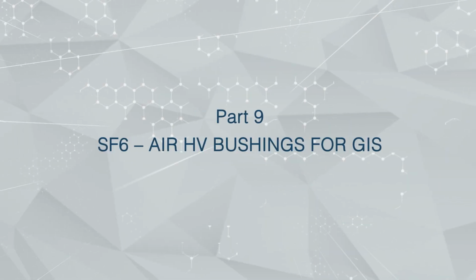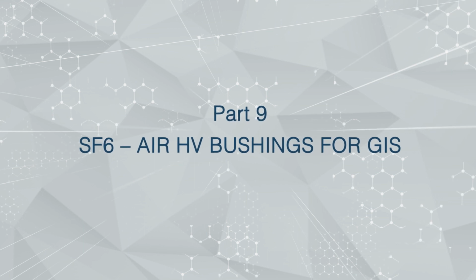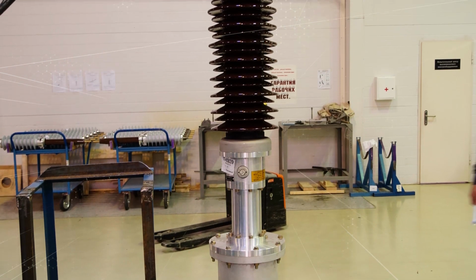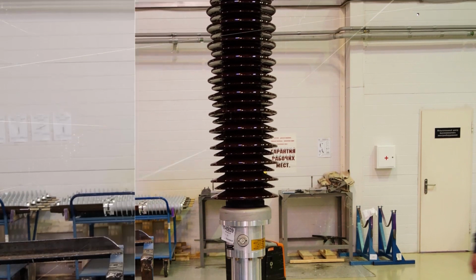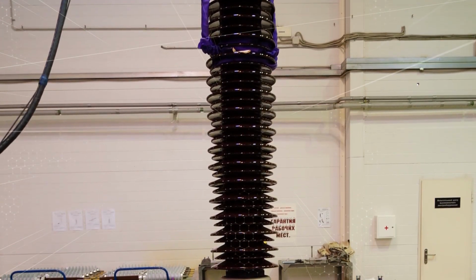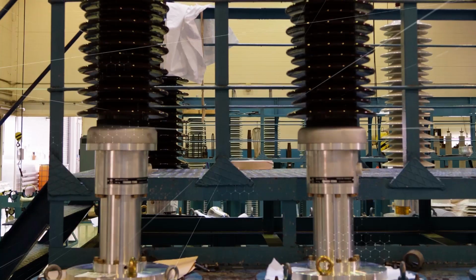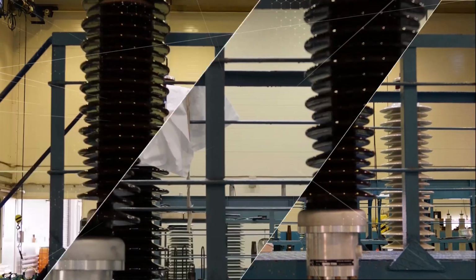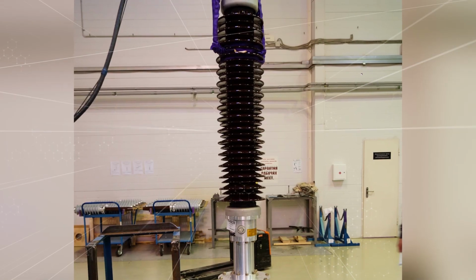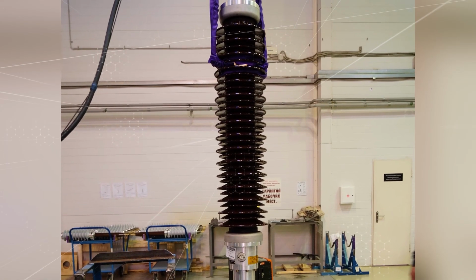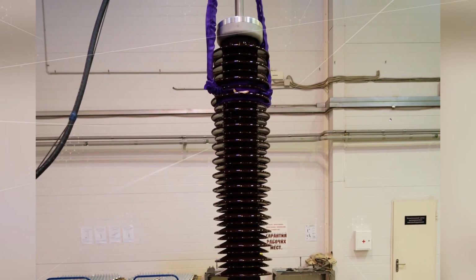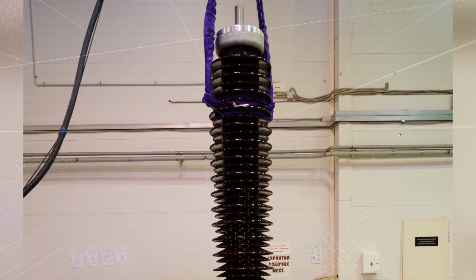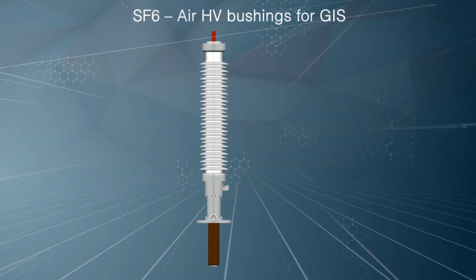SF6 gas-to-air high-voltage bushings for GIS. This group includes special bushings intended for connection of GIS to power lines. The bushing is a feed-through insulator intended for lead-out of the high voltage from a GIS or transformer and is a separate item in terms of construction. In operation, the bottom part of the bushing is positioned inside the GIS or transformer in the gas medium, while its top part is in the open air.